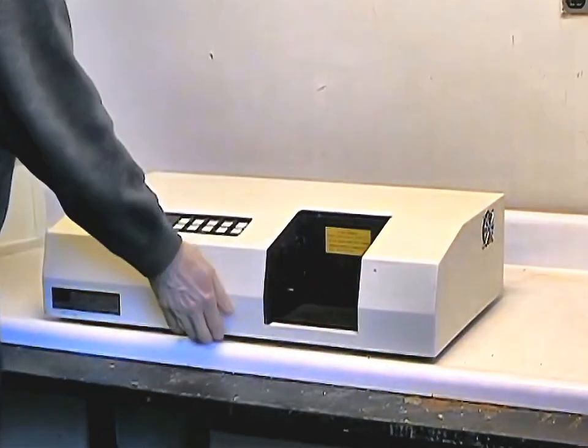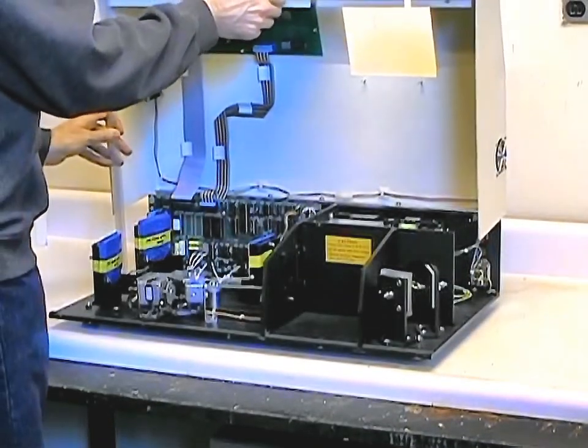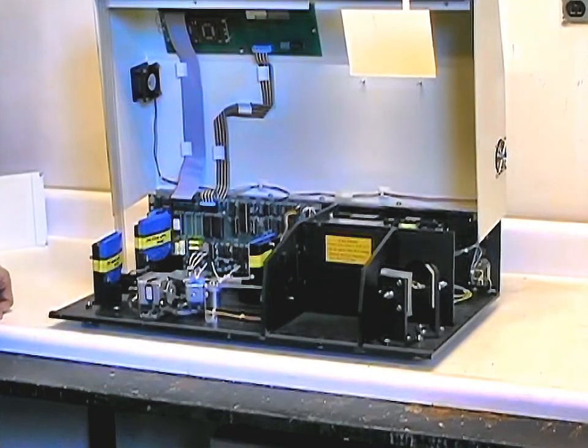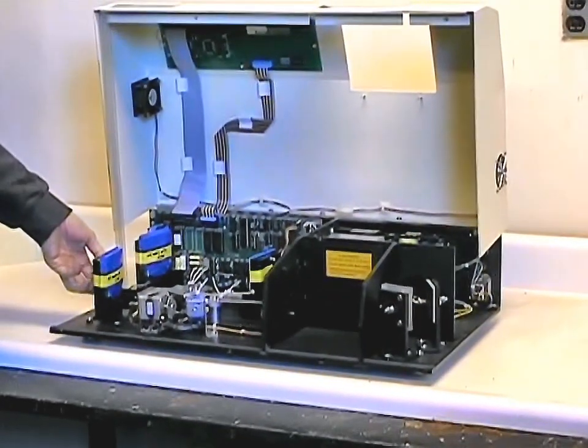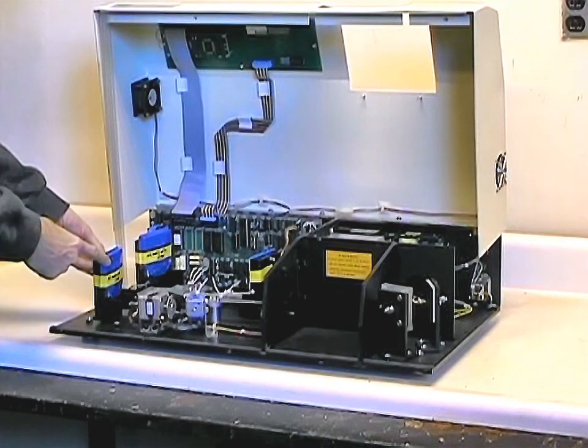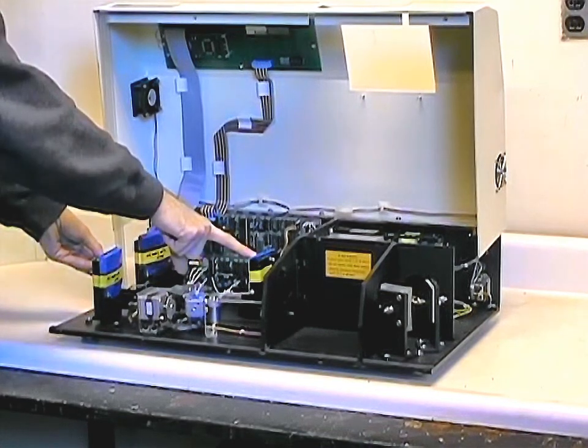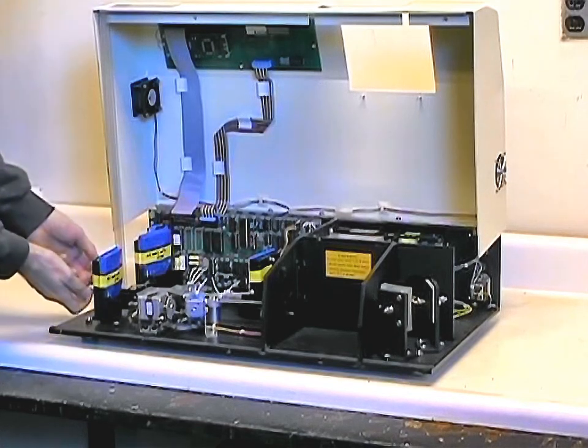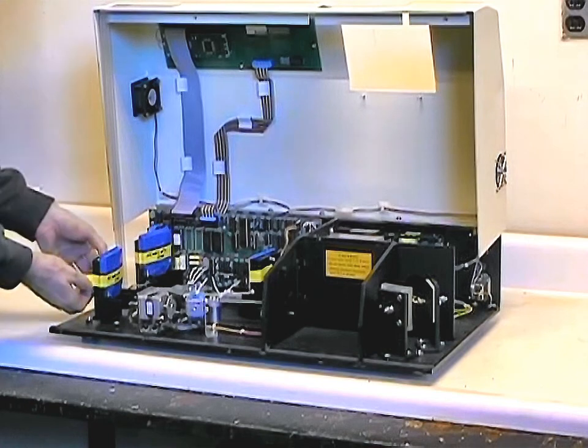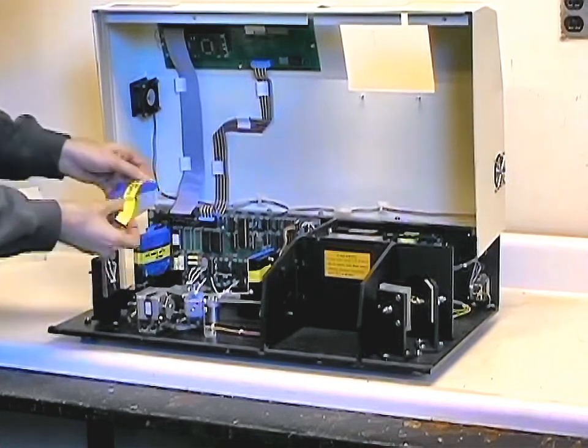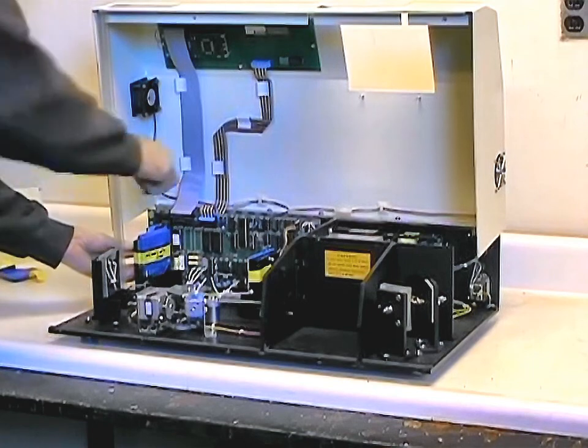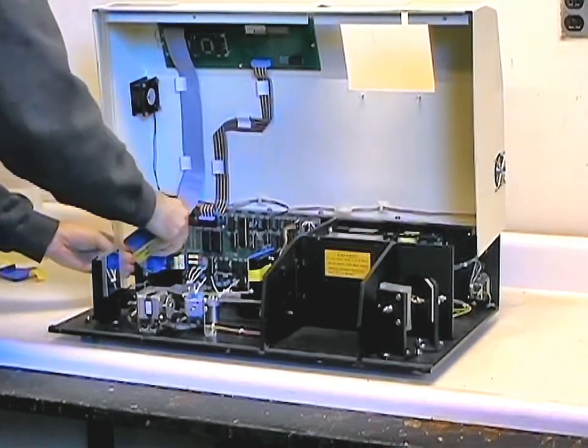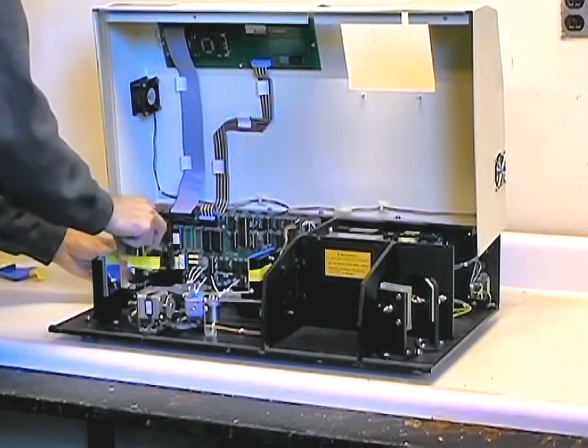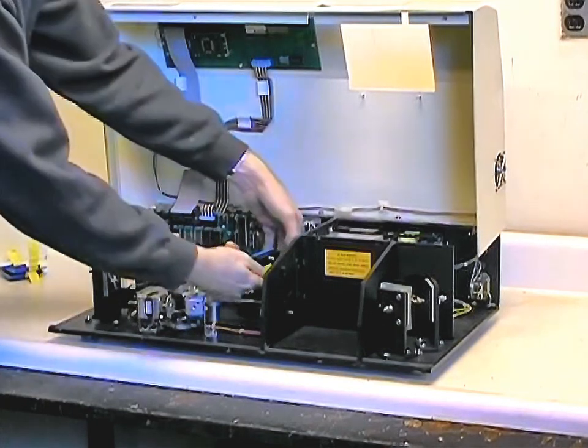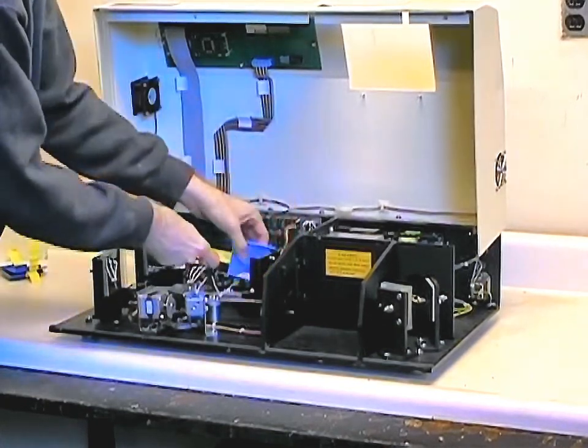The cover is raised, and using a yardstick or appropriate dowel or piece of plastic, the cover is propped open. You can see that there are mirror covers and diffraction grating covers to protect these delicate optical assemblies from dust or fingerprints. Carefully remove the yellow tape holding them in place. Again, it is recommended to keep these covers aside in case the instrument is ever returned for service or maintenance. Be careful not to touch the surface of the mirror or the diffraction grating.